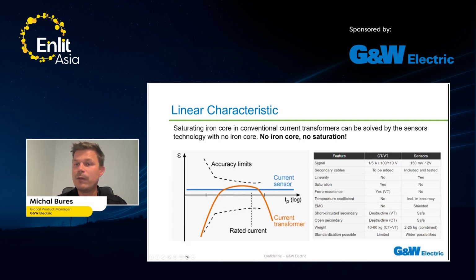It's like 150 millivolts for the current outputs and 2 volts for the voltage outputs. The secondary cable is already included in the sensor, so there's no need to do additional work. As I mentioned, there is linearity, there is no saturation. Also, there is no ferroresonance for the VTs and voltage sensor, of course, so no need for measurement and corrective measures for that. The temperature coefficients are already included in the accuracy. It's shielded. Also, you can short circuit or open the secondary, and it will be safe.